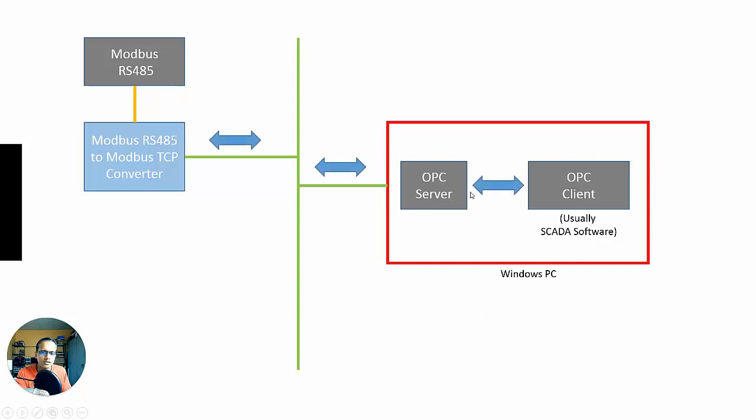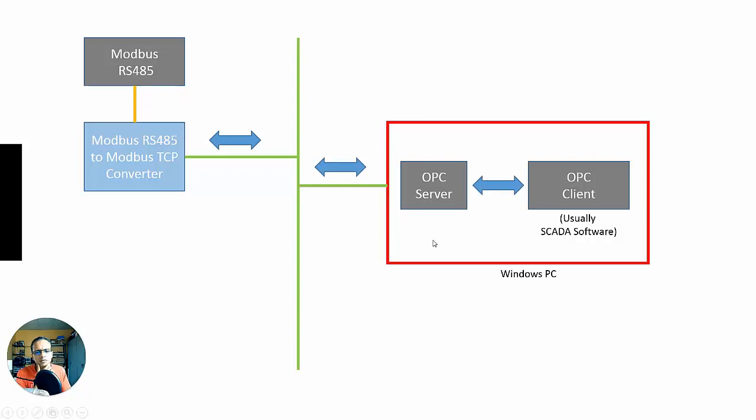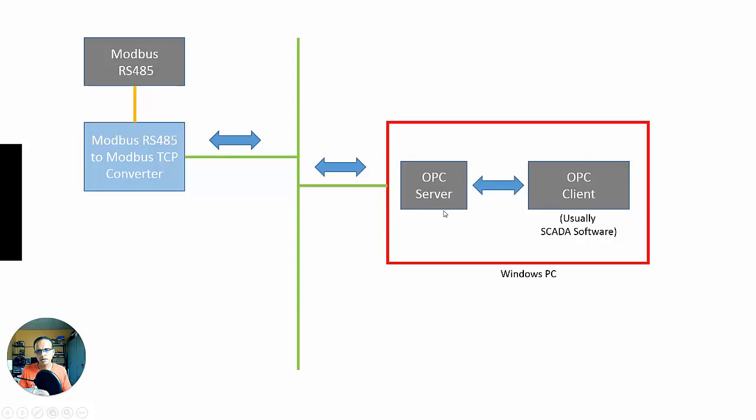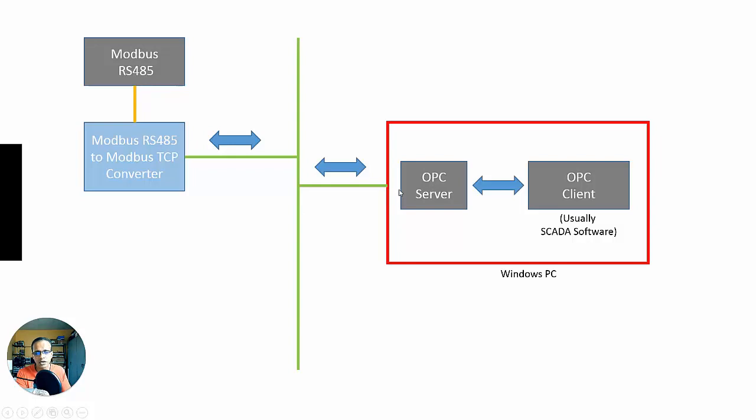So the OPC server here would be acting as a sort of protocol converter, and that was sort of the main point of having that OPC server. So the OPC server, let's say it's from Kepware or Matrikon, two of the big players over the years. They would have support for multiple protocols, like Ethernet IP, all the Allen Bradley stuff, all the Siemens stuff, or tons of different native protocols.